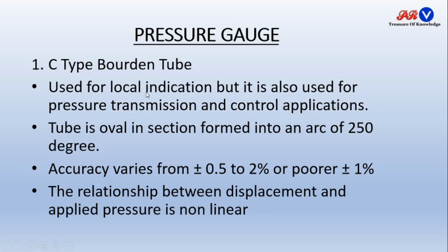Local indication means, just like if we want to measure the pressure of a gas in a gas cylinder, we can use a C-type Bourdon tube. The tube is oval in section, formed into an arc of 250 degrees. This C-type tube has an arc of 250 degrees and accuracy is plus minus 0.5 to 2% or plus minus 1%.